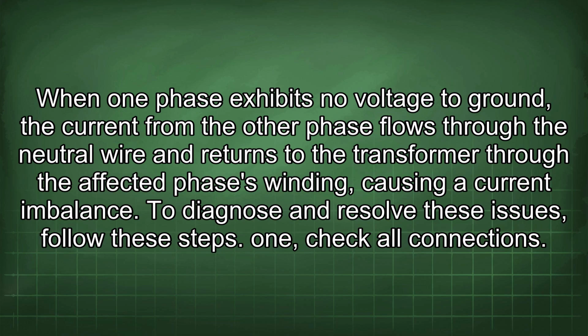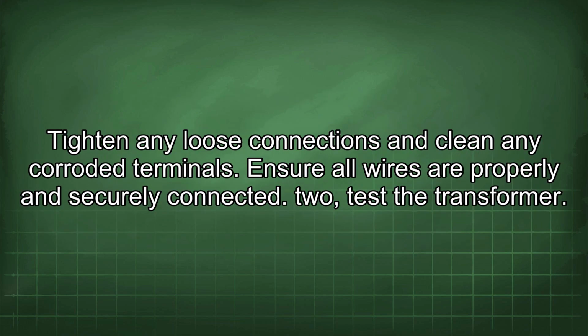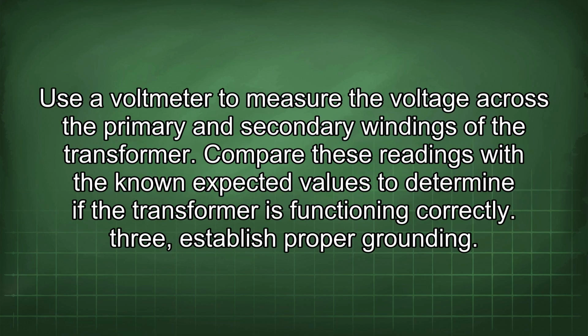To diagnose and resolve these issues, follow these steps. 1. Check all connections. Tighten any loose connections and clean any corroded terminals. Ensure all wires are properly and securely connected. 2. Test the transformer. Use a voltmeter to measure the voltage across the primary and secondary windings of the transformer. Compare these readings with the known expected values to determine if the transformer is functioning correctly.